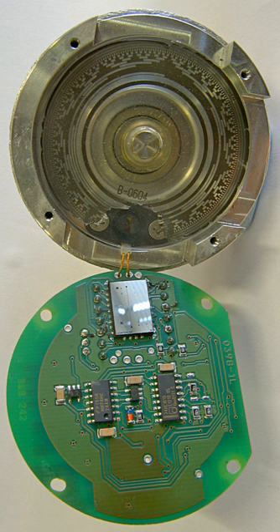Topic: Battery-powered multi-turn encoder. This type of encoder uses a battery for retaining the counts across power cycles. It uses energy-conserving electrical design to detect the movements. Topic: Geared multi-turn encoder. These encoders use a train of gears to mechanically store the number of revolutions. The position of the single gears is detected with one of the above-mentioned technologies.